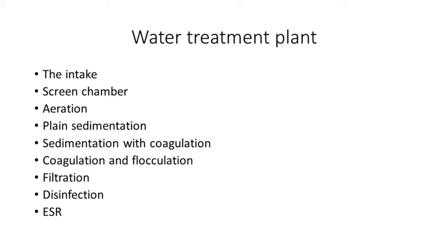Again, we also discuss the jar test. The jar test is an apparatus which is used to find out the optimum dose of coagulant. From that you can identify the dose of coagulant which gives the best floc, and that correct dose is the optimum dose of coagulant. From that you can minimize the wastage of chemical in the coagulation process.